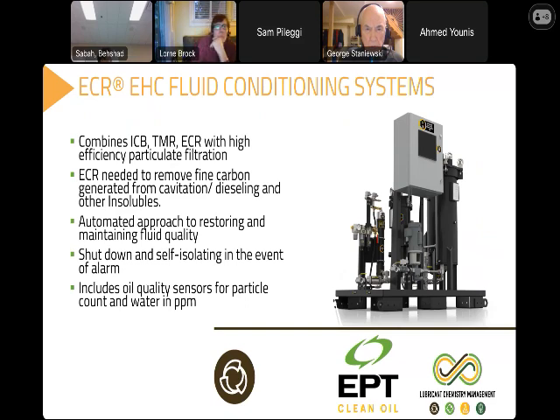Regarding today's presentation, Andrew's going to talk to you shortly. Our company has a combination product called ECR. It combines electrostatics, ion exchange resins, nitrogen generators, high efficiency filtration, inline oil quality sensors, automation, SCADA controls, Internet of Things. On EHC systems, this manages quite a wide range of contamination, okay? And EHC applications are complicated because of the high pressure fluids and the stress that these fluids are put under. In cases of cavitation or microdieseling, we're also getting carbon. We're getting a pretty broad range of contamination that has to be addressed, and we require different technologies to remove it.